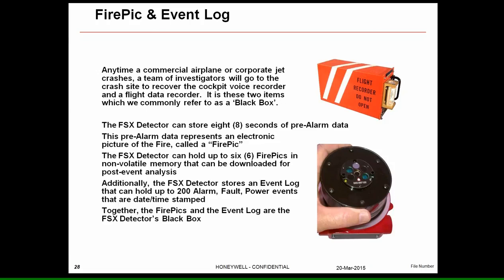We can retrieve that data and have a resident PhD in Lincolnshire who can analyze the FirePic and possibly postulate the cause of the fire. For the FSX detector, a single FirePic is eight seconds of pre-alarm data leading up to the declaration of fire. We can store six of these events simultaneously; when a seventh event occurs, it overwrites the oldest, so you always have the last six events recorded on that detector.